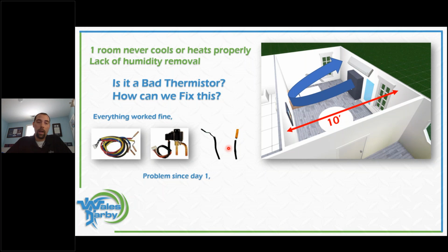It's going to hit this little air thermistor in the top of the unit. And yeah, the room's 80 degrees, but I got 64-degree air. Well, maybe I got 50-degree air coming back. My set point is 64. It's going to shut the system down, and I'm not going to pull humidity out, and I'm not going to cool it properly. So this is a big complaint.